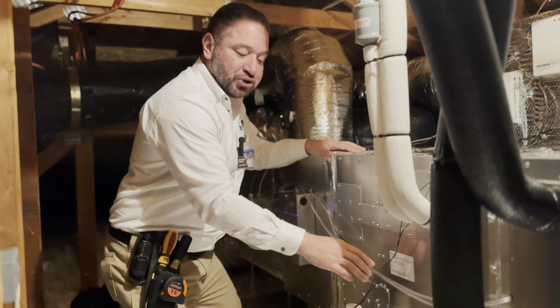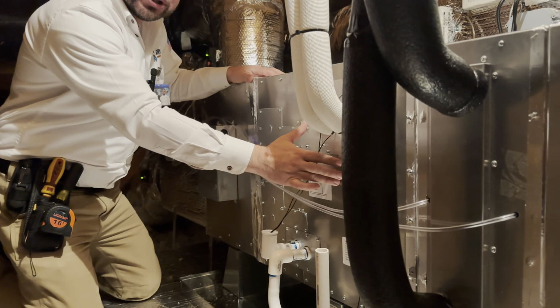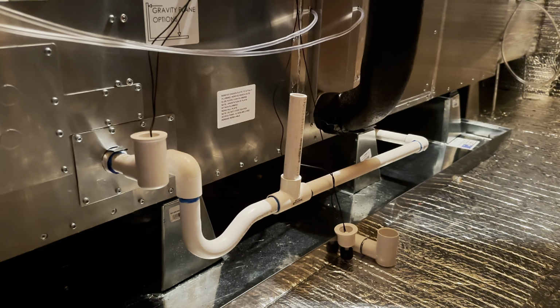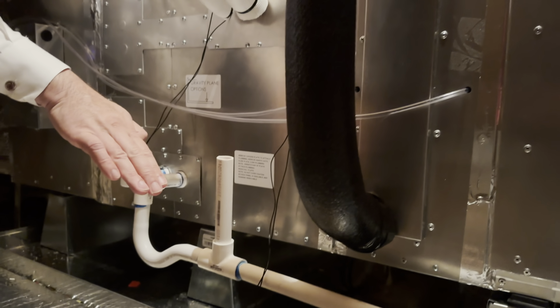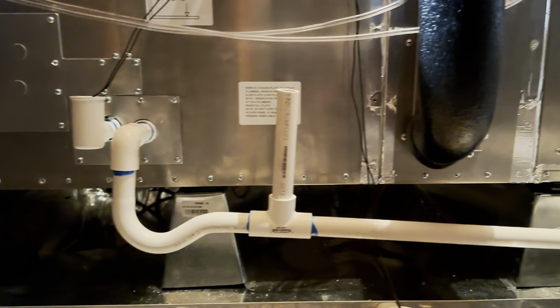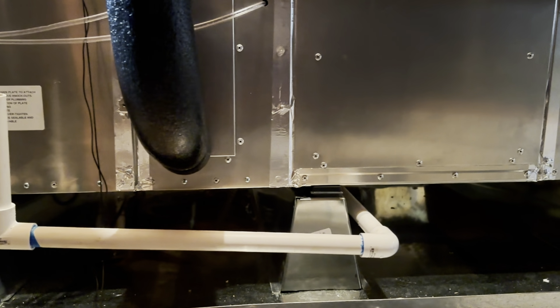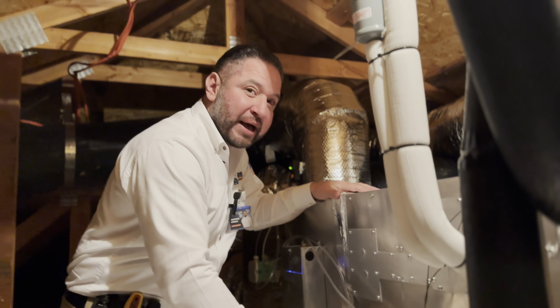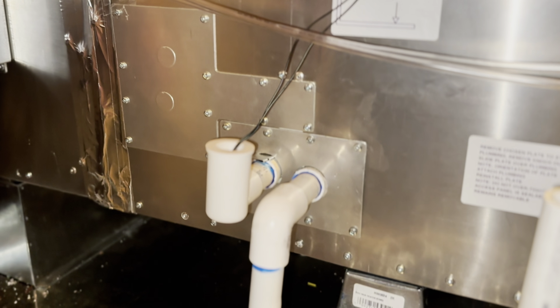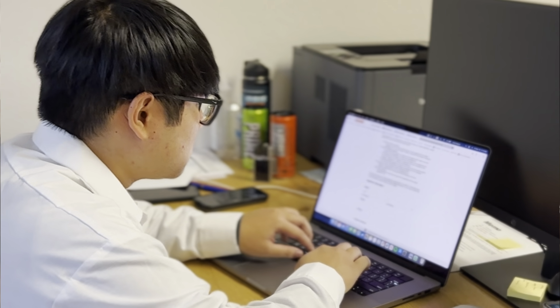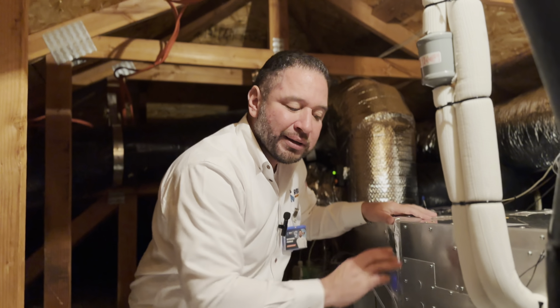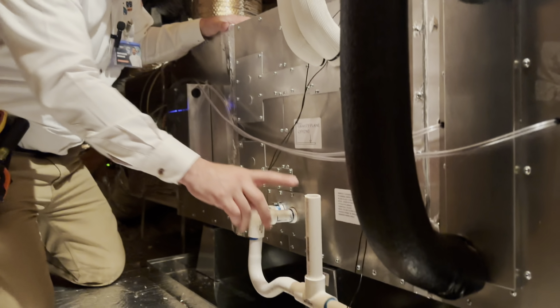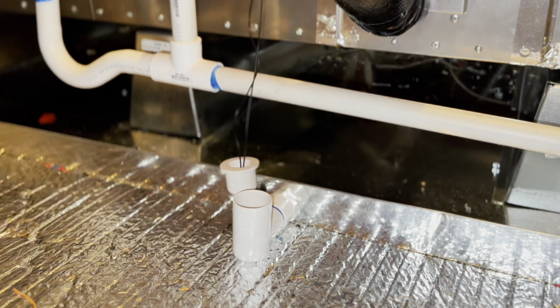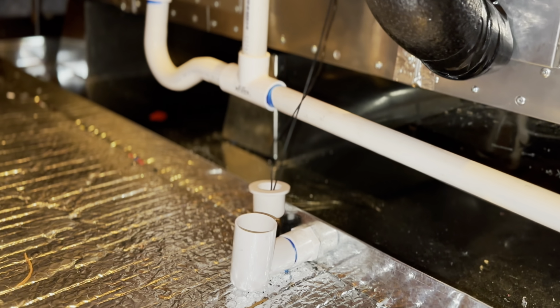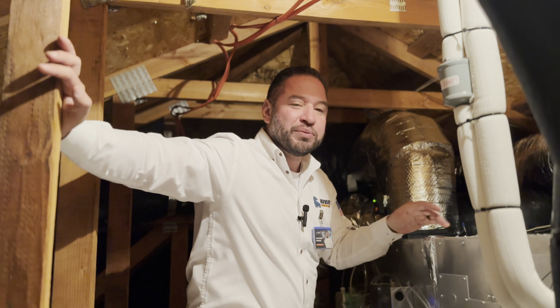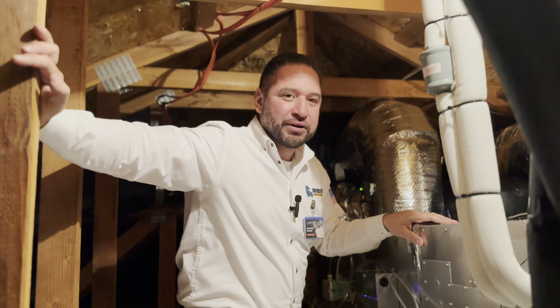So this is going to drain the water that condenses when it's cooling your home. And this right here is an air gap. It's going to make sure that water flows nice and freely. And we want to make sure that slope is about 1/4 inch per foot to make sure that the water goes out nice and smoothly. Now, if this fails, that's why we have this backup. This float switch will go up, tell the system to turn off, and then we'll get notification and we make sure that we come out to see exactly what's going on. The third safety feature, if this fails and this fails, we have this third option here, which is kind of like the all fail safe. So we'll make sure you don't have any leaks in your attic. We'll keep your home nice and dry and make sure it's nice and warm and cool all year long.